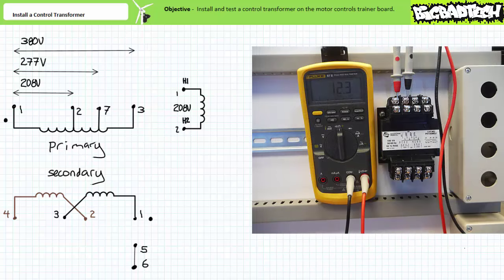An ohmmeter used to check the resistance of the primary windings from 1 to 2 shows continuity and a resistance of 12-ish ohms.